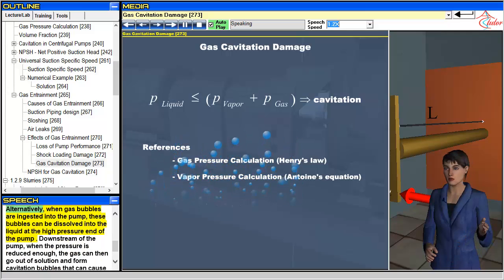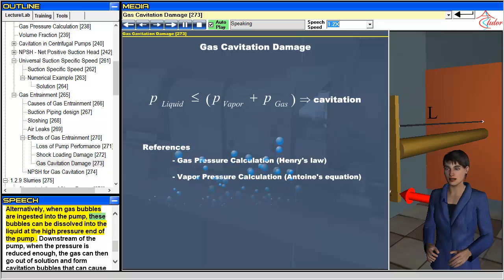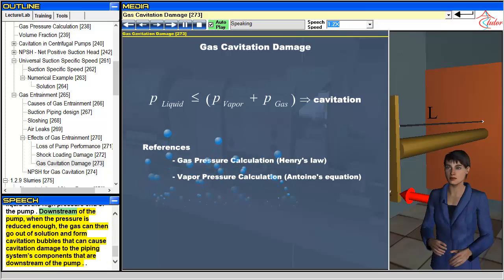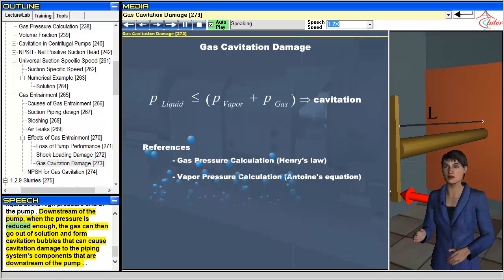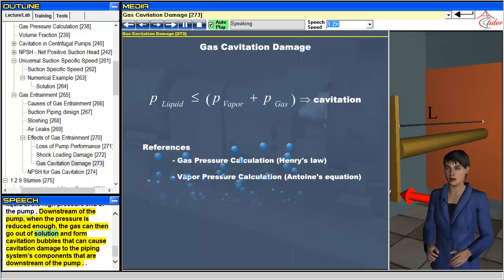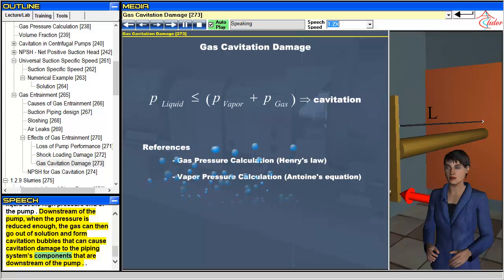Alternatively, when gas bubbles are ingested into the pump, these bubbles can be dissolved into the liquid at the high-pressure end of the pump. Downstream of the pump, when the pressure is reduced enough, the gas can then go out of solution and form cavitation bubbles that can cause cavitation damage to the piping system's components that are downstream of the pump.